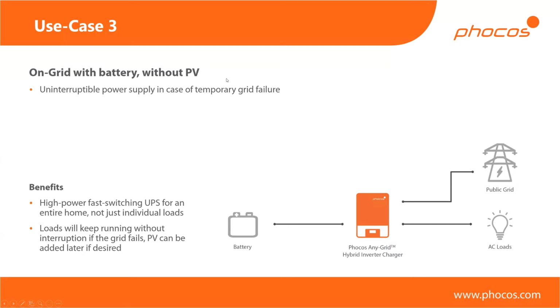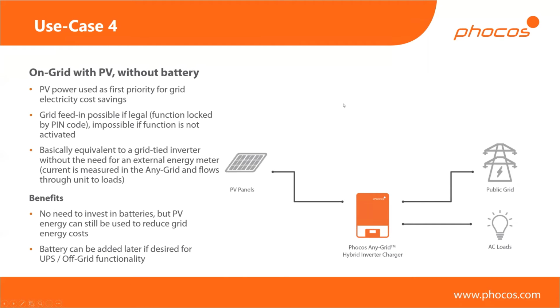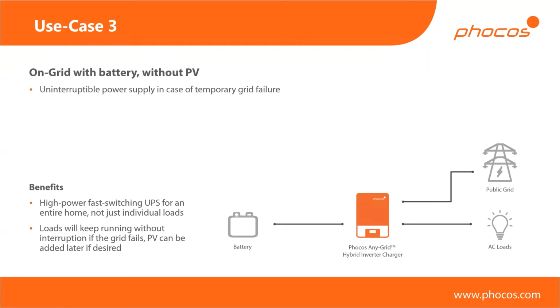So someone is asking if this can be AC coupled. I believe what you mean by AC coupling is connecting a grid injection inverter on the AC output. That you cannot do. So the AC output is unidirectional. It's only for providing power to loads. It cannot accept power from a grid-connected inverter that you would connect to it.